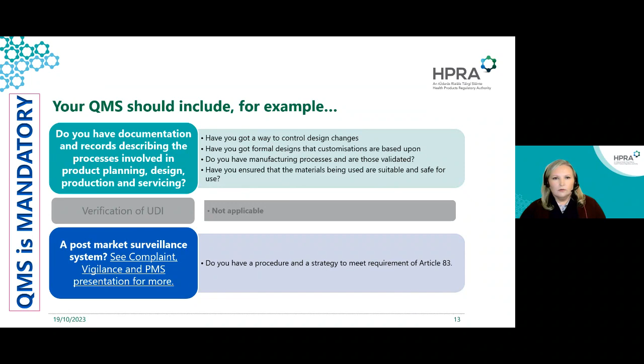But to verify compliance with this requirement, the expectation is that the manufacturer would have a procedure outlining the approach to post-market surveillance, plus the manufacturer would have generated the related outputs from that process, such as a PMS plan and a report, and perhaps a post-market surveillance update report where required. Part J outlines the requirement to have mechanisms to communicate with relevant parties as needed. This includes communicating with the likes of the HPRA or other competent authorities, communicating with notified bodies if relevant, and also other economic operators, customers, and users.